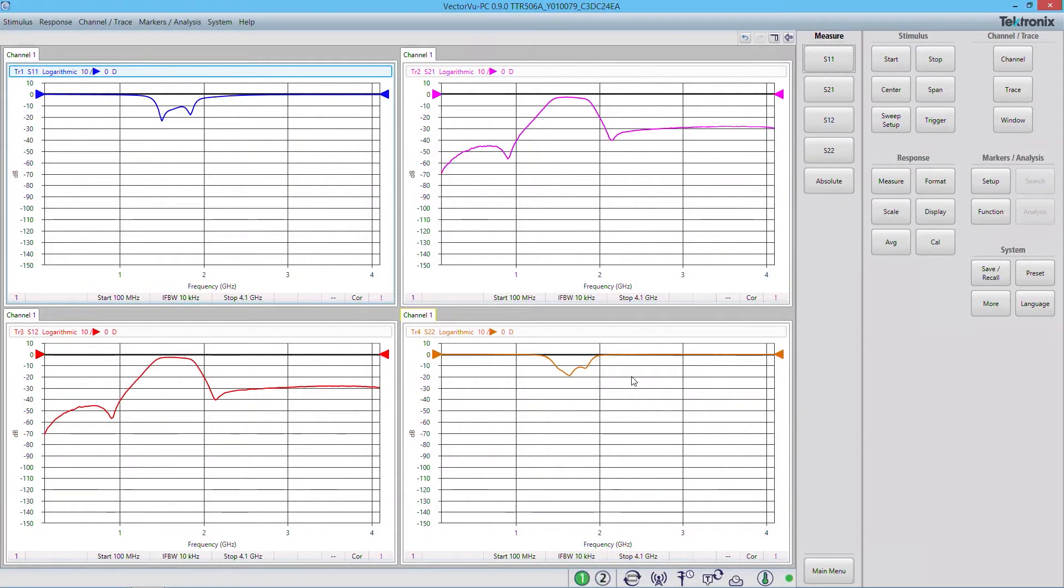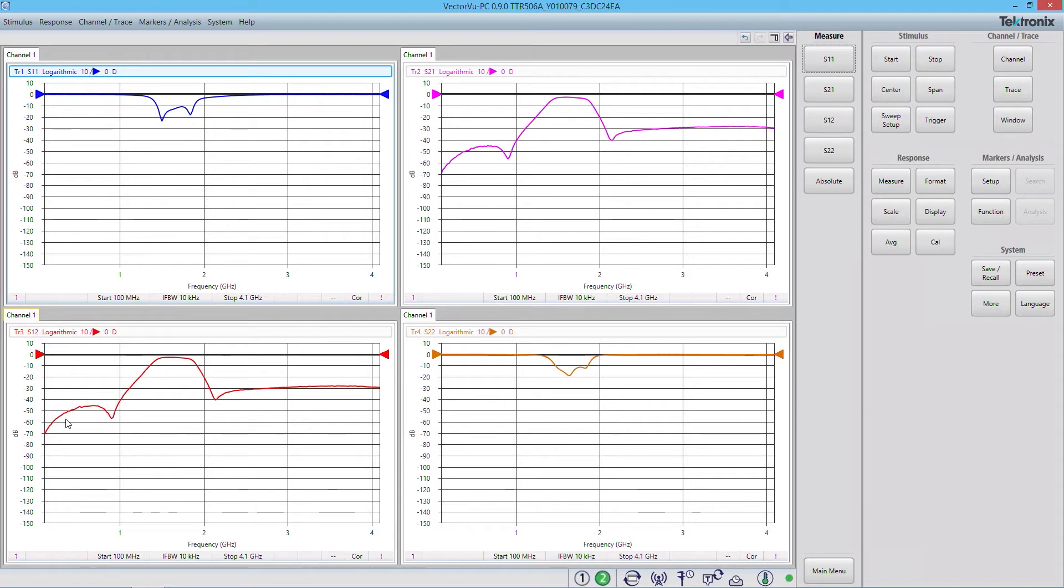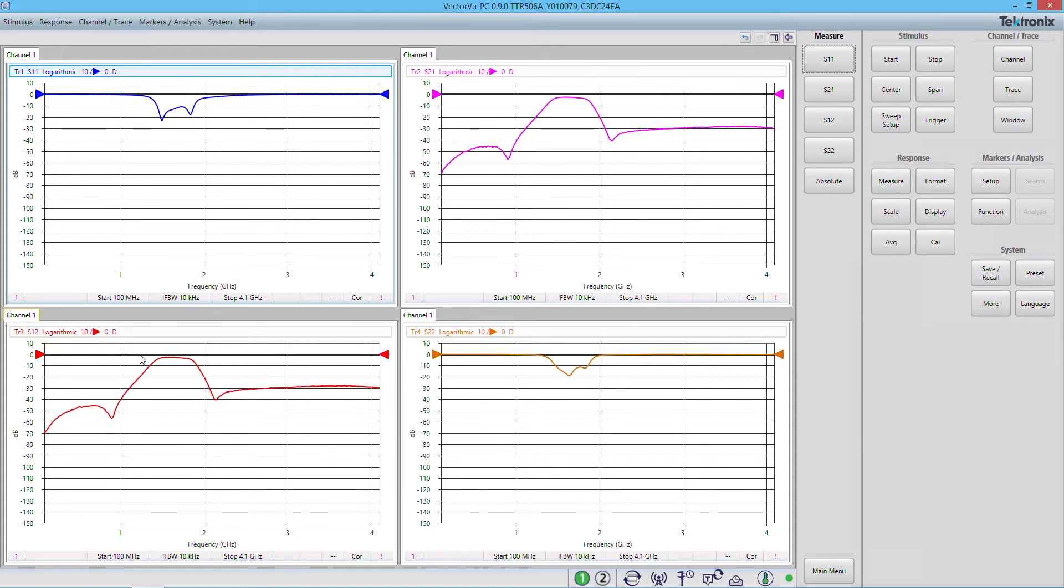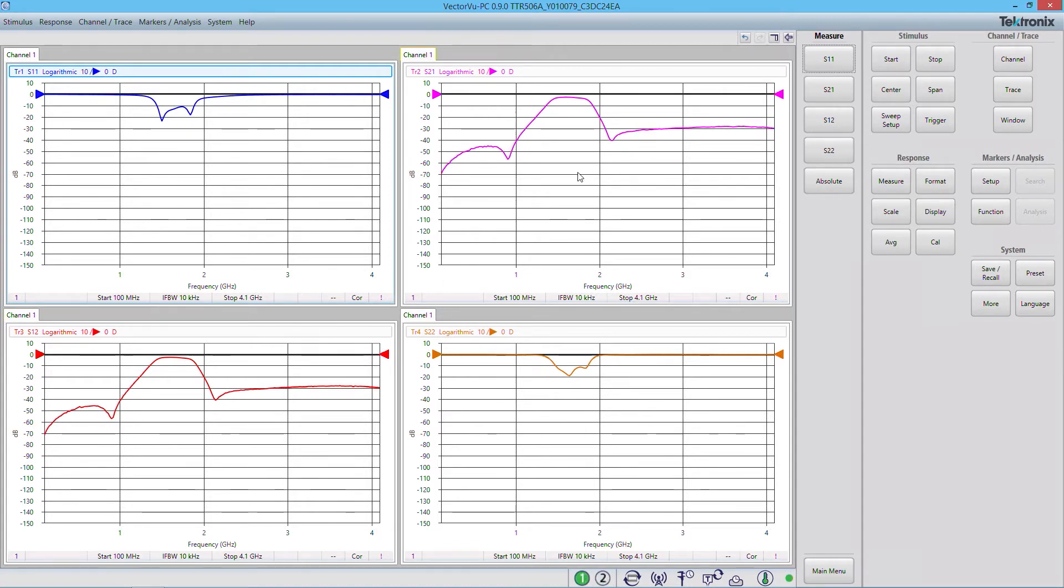Now if you take a look at the screen here, we're going to see that instantly our device is being measured. So we're sweeping constantly across each frequency range through each one of the pathways in the device. You can see that response here. The one that I'm primarily interested in is this S21 measurement, and we're going to get to that later.